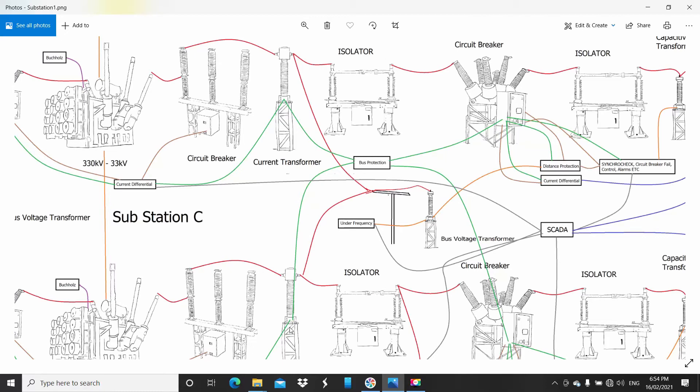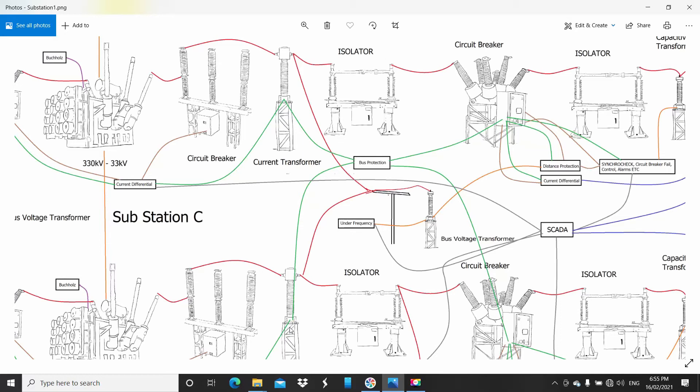You can see we have a bus voltage transformer. That would be used for the different protection systems that hang off the line. In this case, I've also got under-frequency protection. The whole idea of under-frequency is when there's not enough power in the system, the frequency starts to sag, starts to drop. When it hits a predefined limit, it'll trip, but it'll hit the timing before it goes to allow networks to manually go ahead and try and find the power savings it requires.